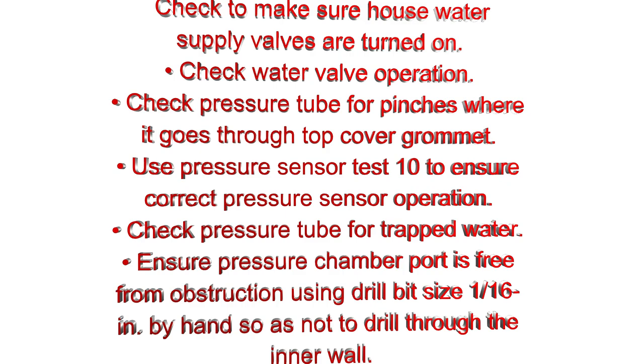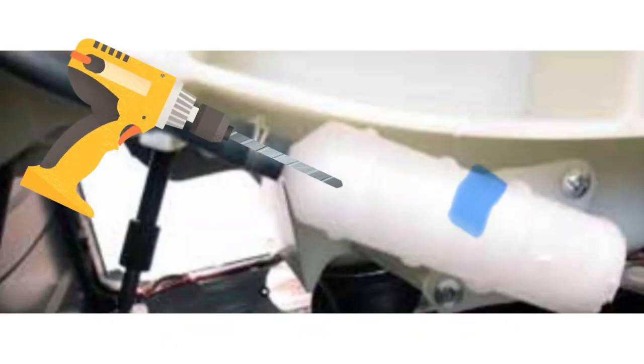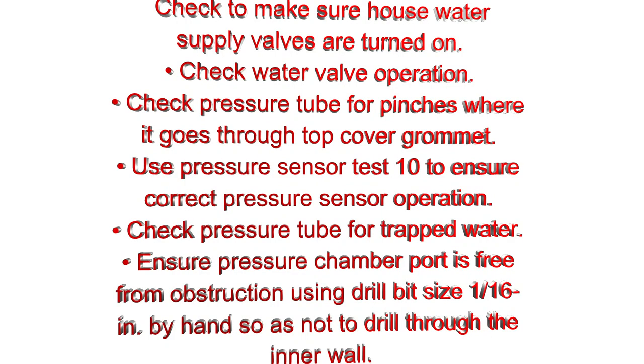Use pressure sensor test 10 to ensure correct pressure sensor operation. Check the pressure tube for trapped water. Ensure the pressure chamber port is free from obstruction using a 1/16 in drill bit by hand, so as not to drill through the inner wall.